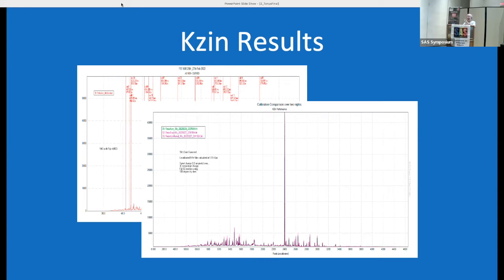I did it again and did what you're not supposed to do, and I slewed the grating 1,000 angstroms into the blue and brought it back, and on a 4,500 pixel dispersion axis, it had moved by 3 pixels. Now, I'm not excusing the 3 pixels. I know where that is. It's in the bearing. But it is so stable as to be scary.